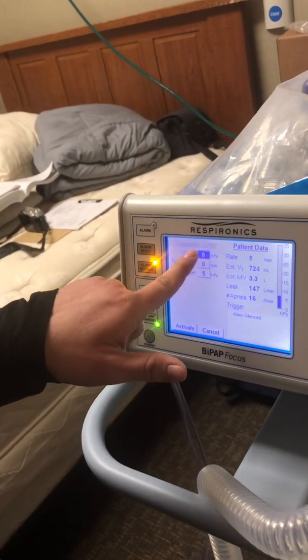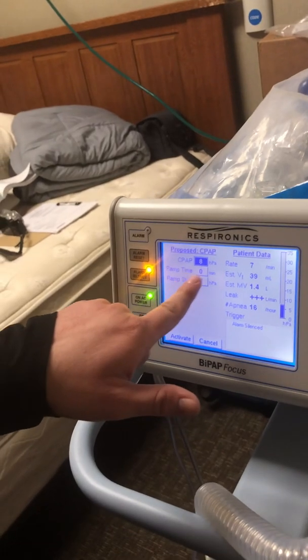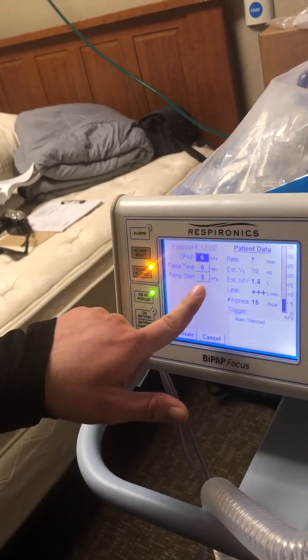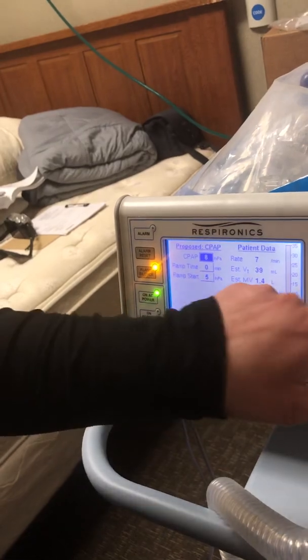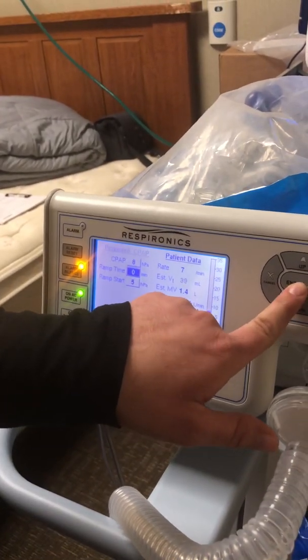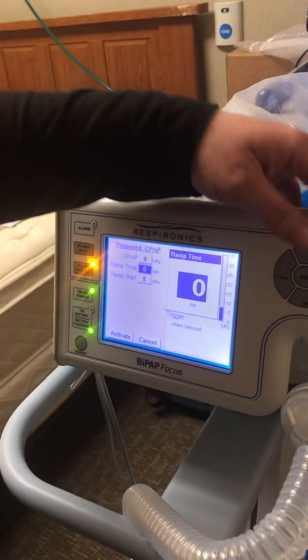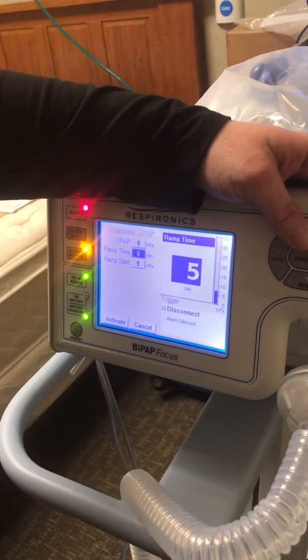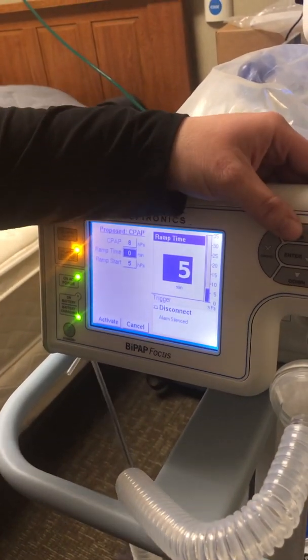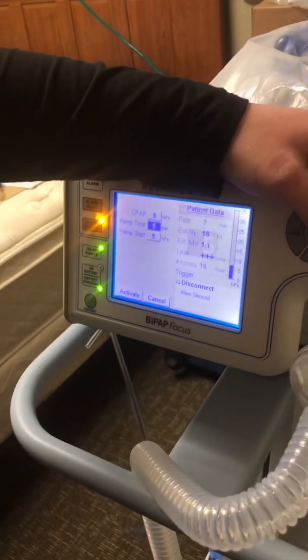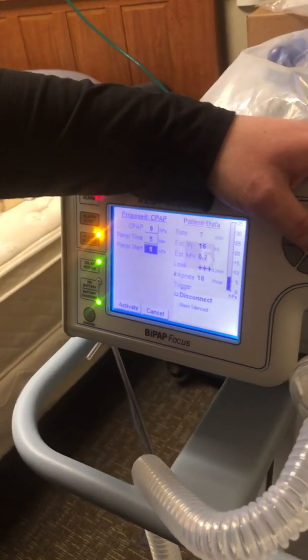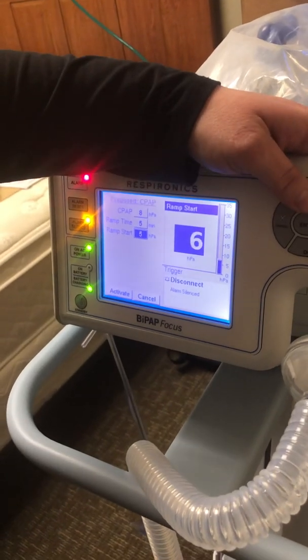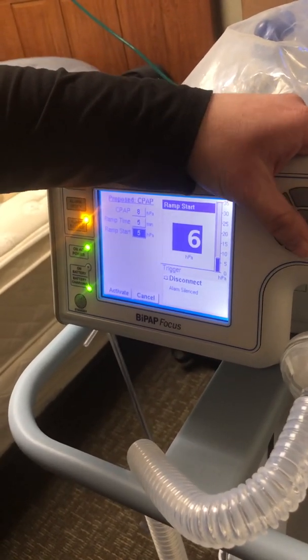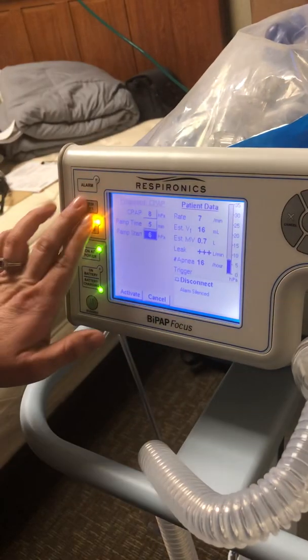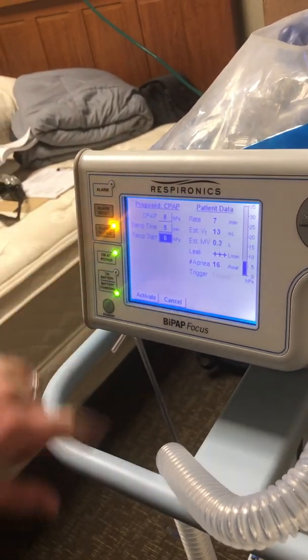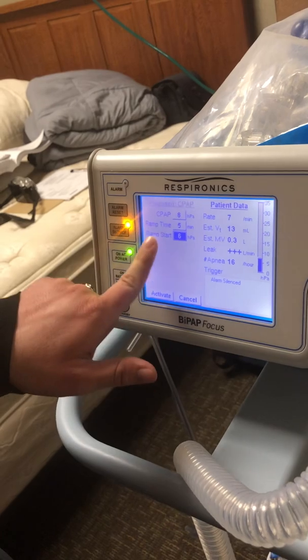And so here we have CPAP set at 8, and you need to have ramp time and a ramp start. So however many minutes you want their ramp time to be, you can select it and move up the ramp time. So every 5 minutes that ramp time will begin, and you'll hit enter. And so the ramp starts, and you can change it to 6, anything like that. Just that way you can change your settings.